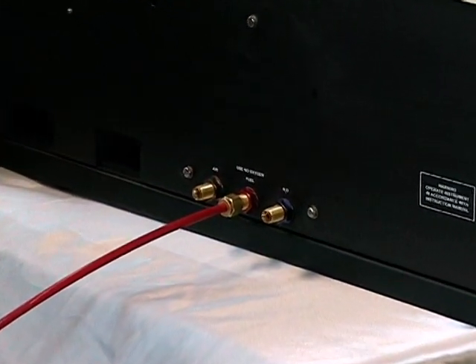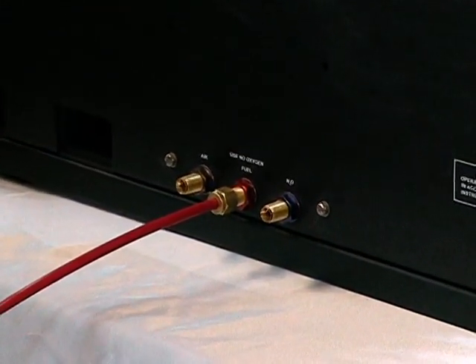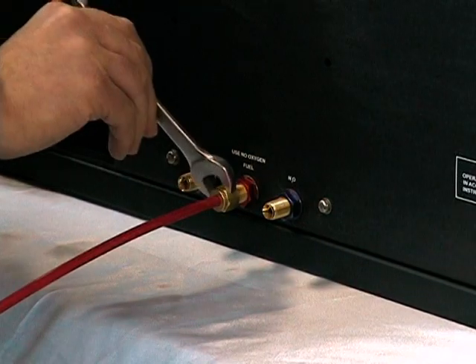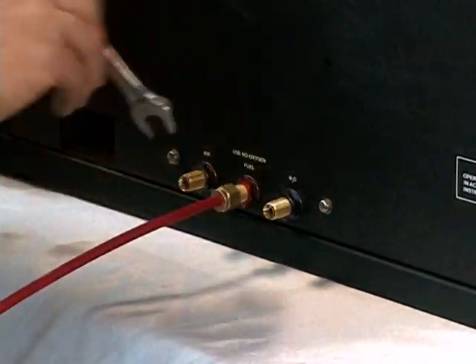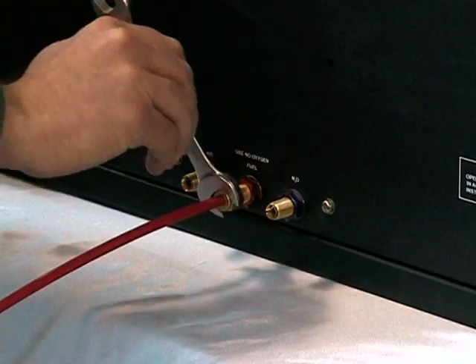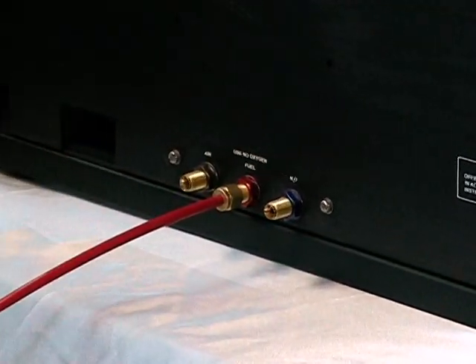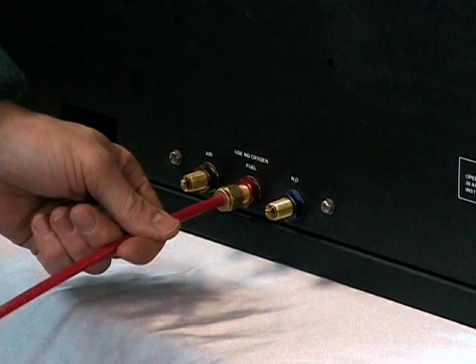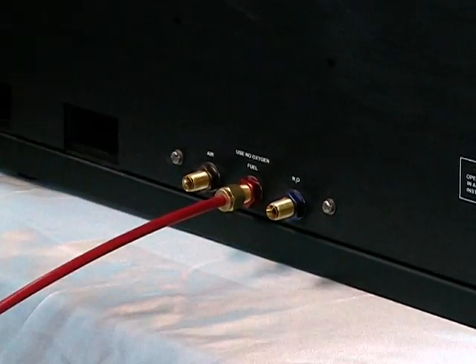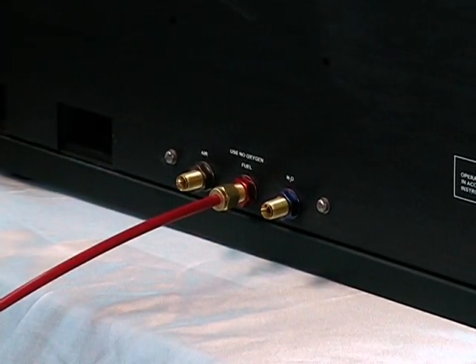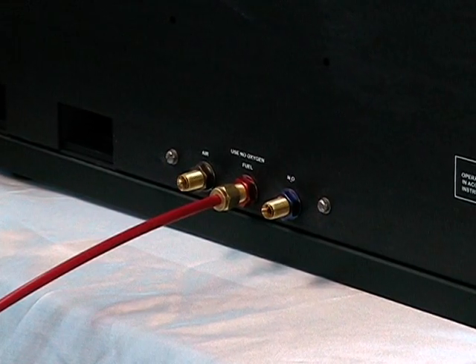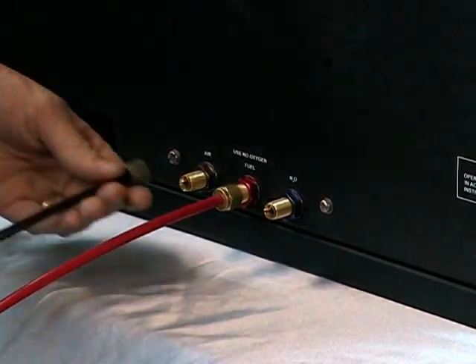Once the fitting is hand tight, tighten it with a wrench 1 to 1.5 times, and this will create a gas-tight fitting where the brass ferrule will grab the tubing and give a good seal. Repeat this for the other lines, and we will proceed to install the instrument on the laboratory bench.